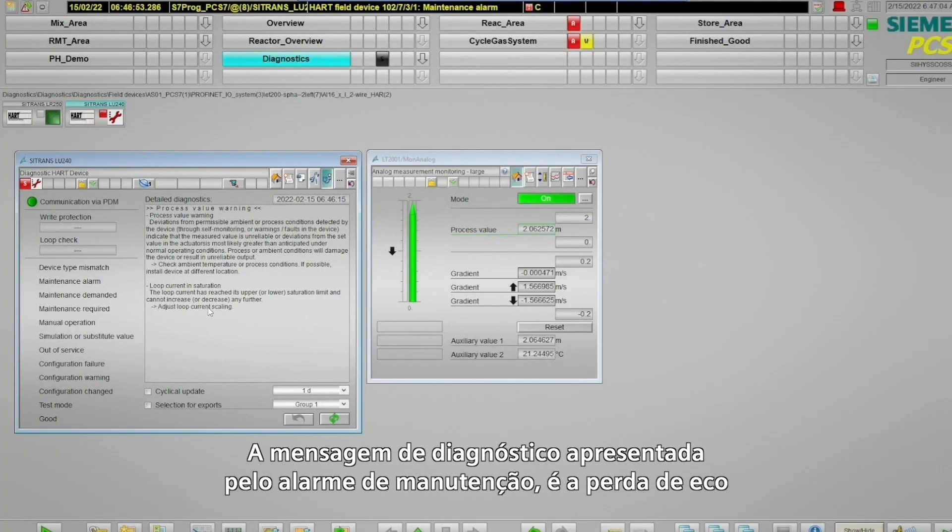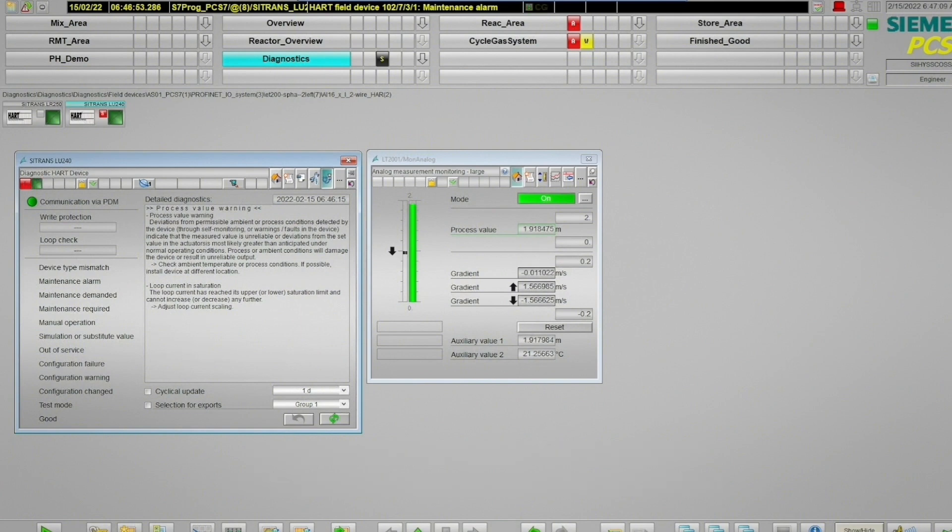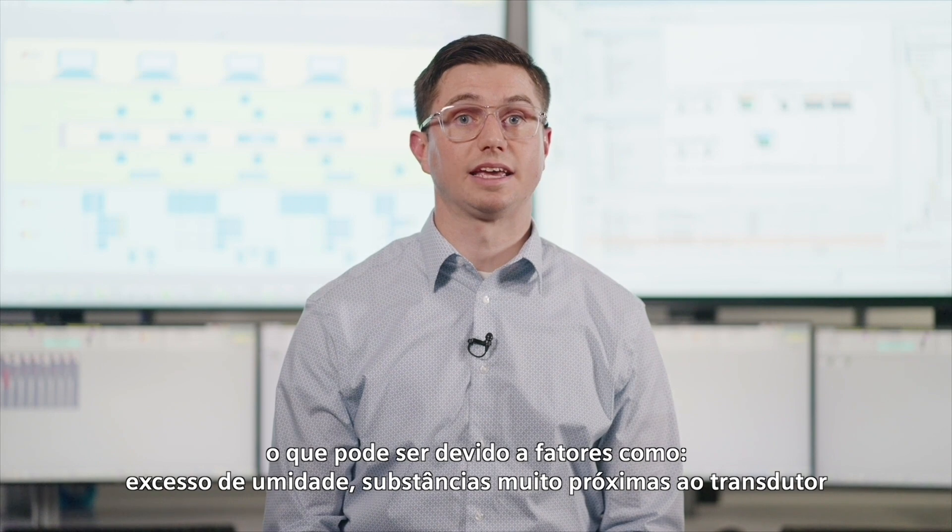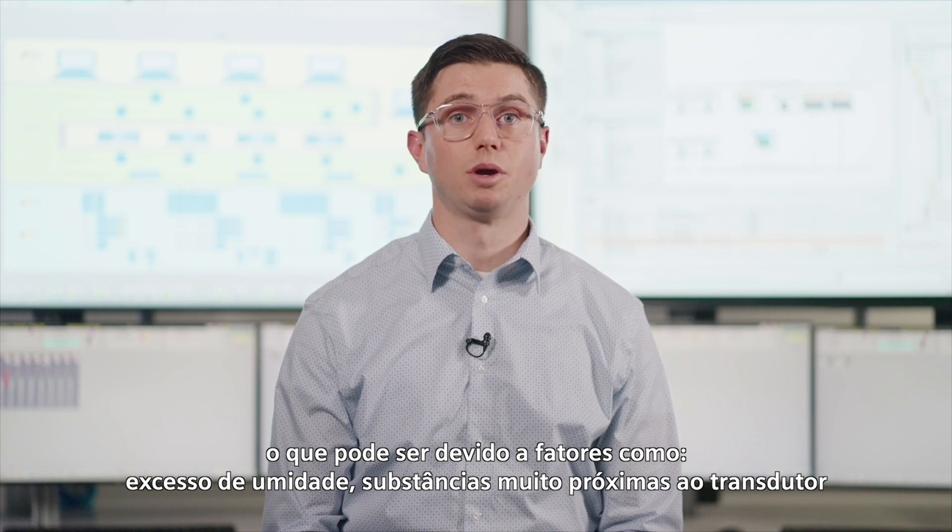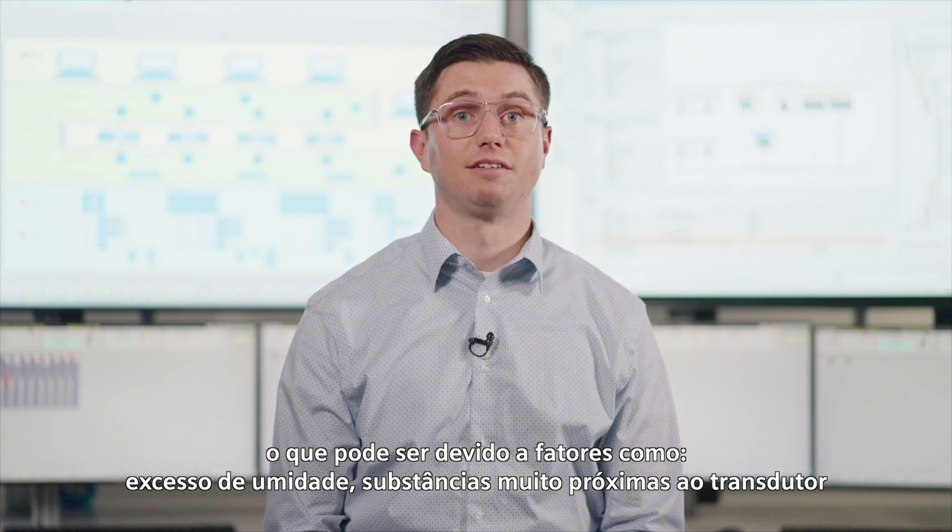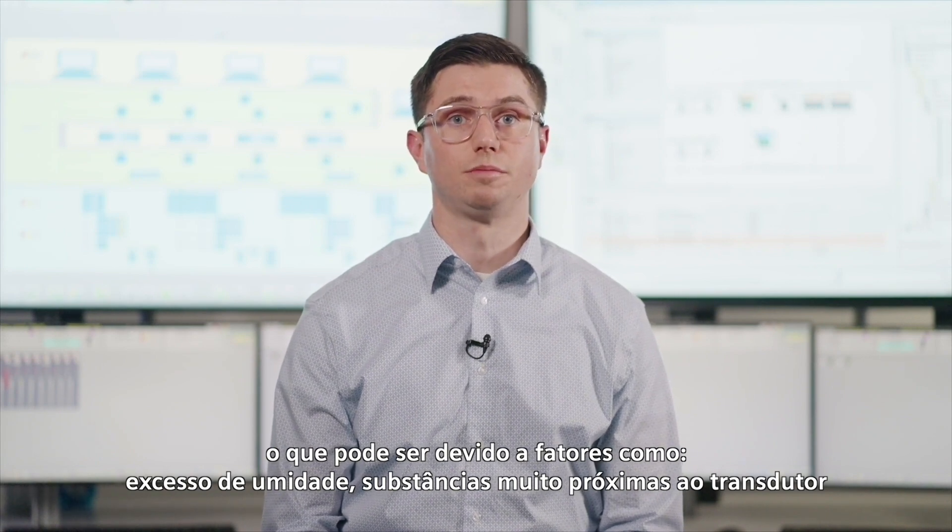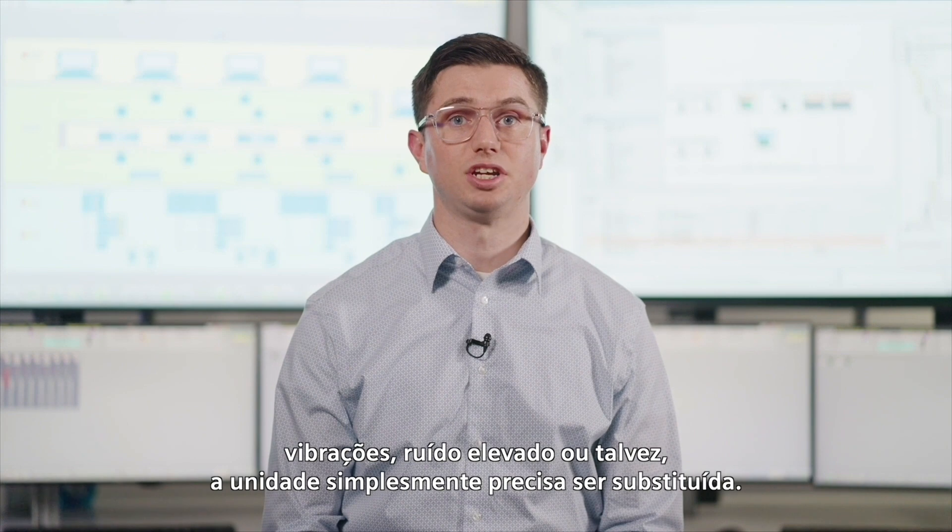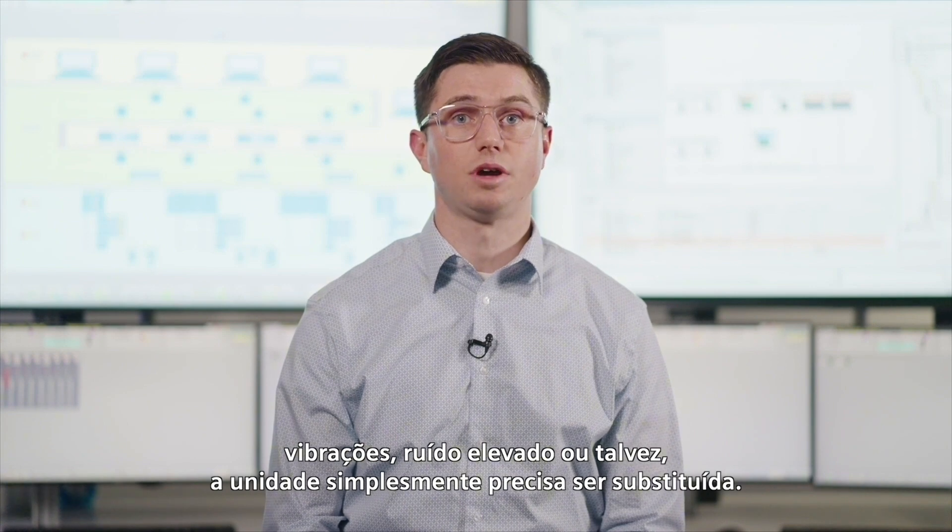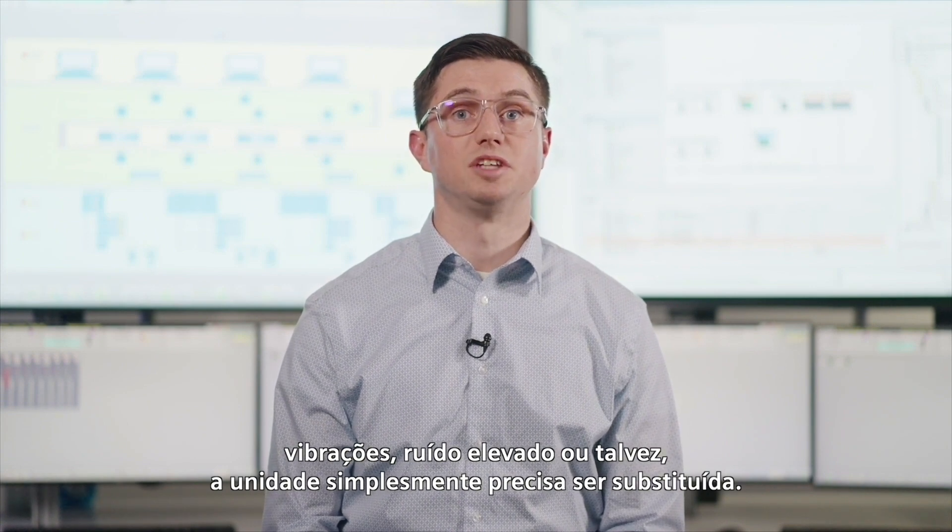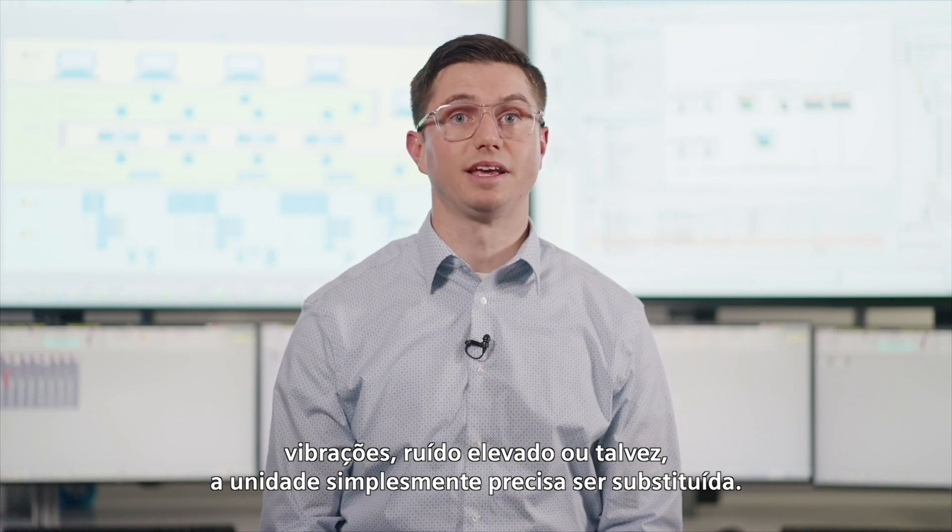The diagnostics message indicates that the maintenance alarm is from a loss of echo, which could be due to factors like excessive moisture buildup, material being too close to the transducer, vibrations, nozzle height, or maybe that this unit simply needs to be replaced.